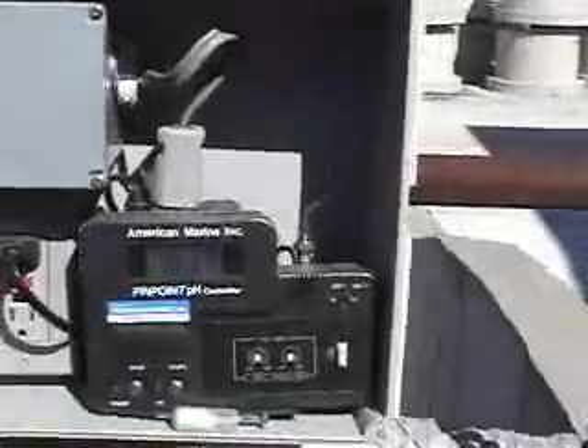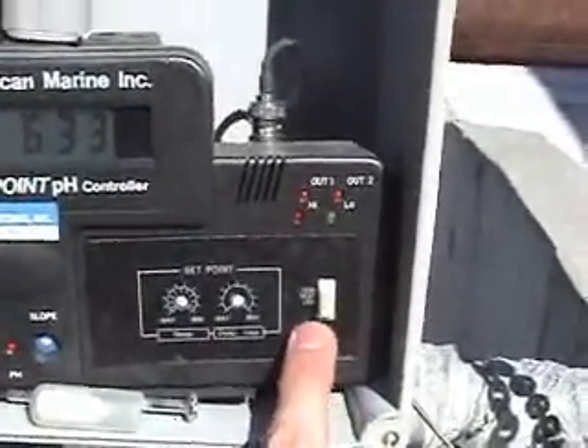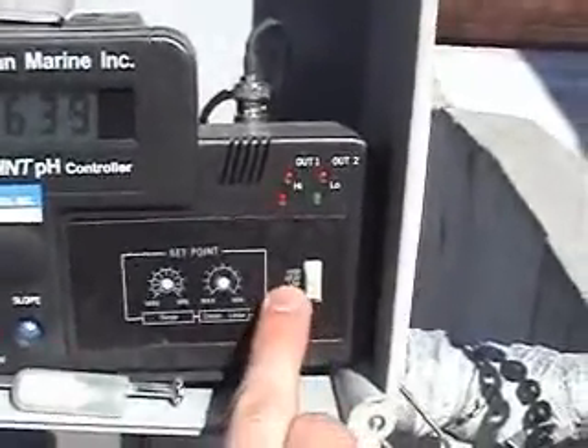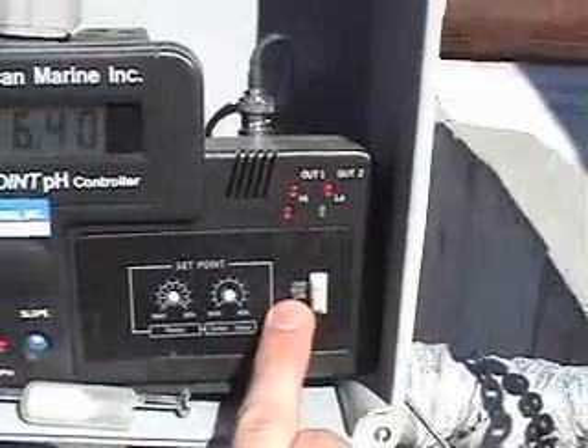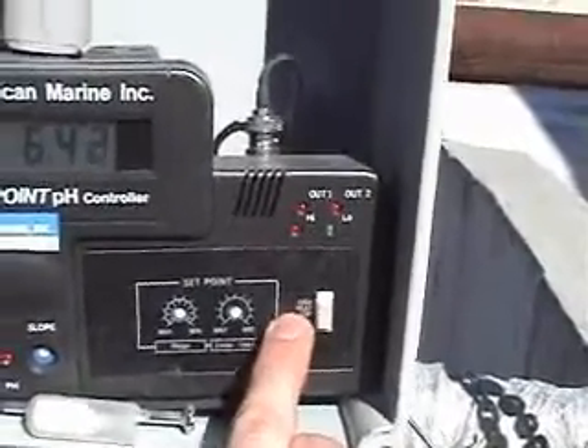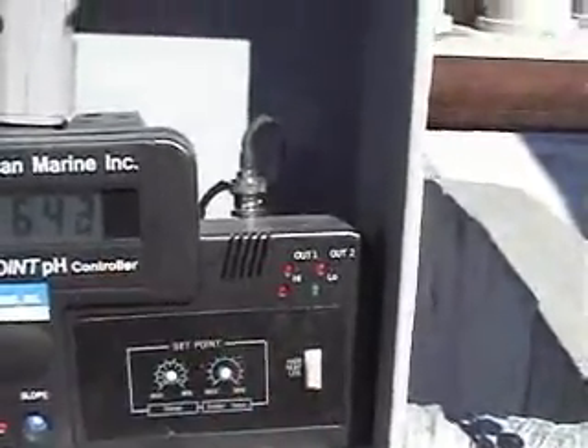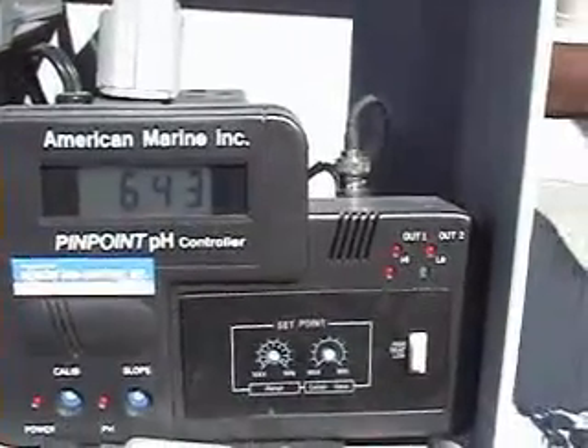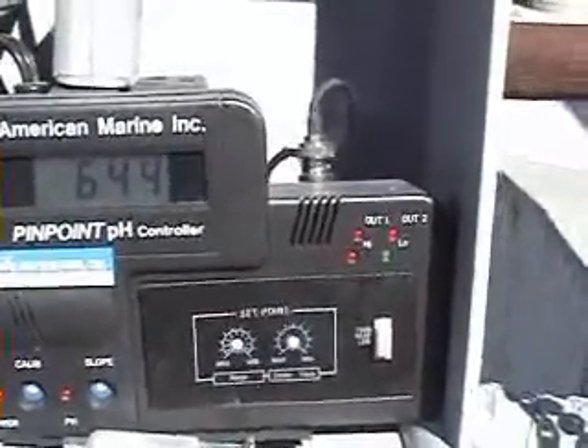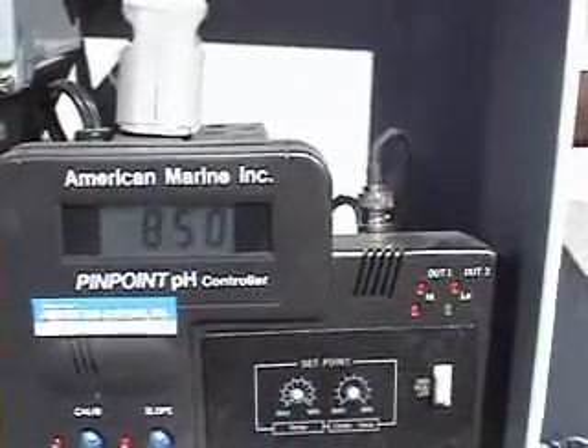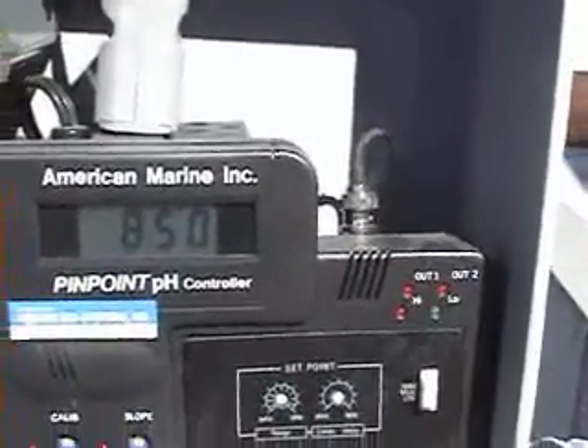Now, what happens with your pH system here? We have 3 different settings over here. Right now we're on the center reading, which is the actual read position, which will show the actual pH of the washout pit behind the pH system here. If I push it up, we'll get the high limit, which is 8.50.